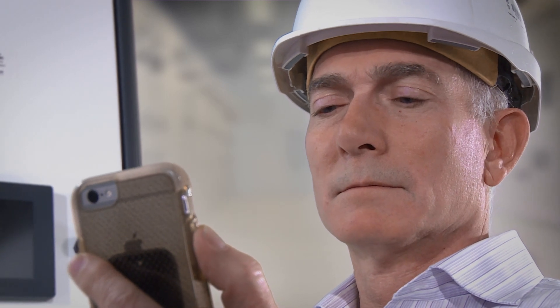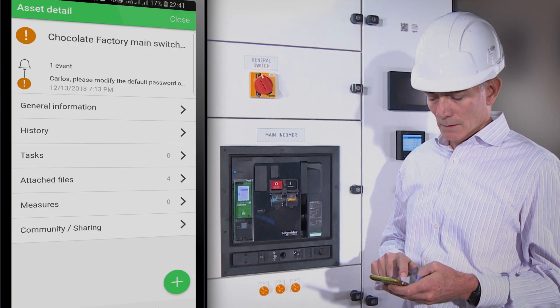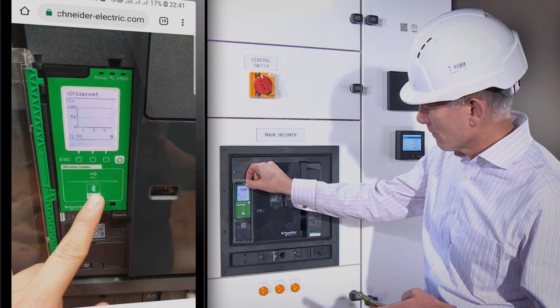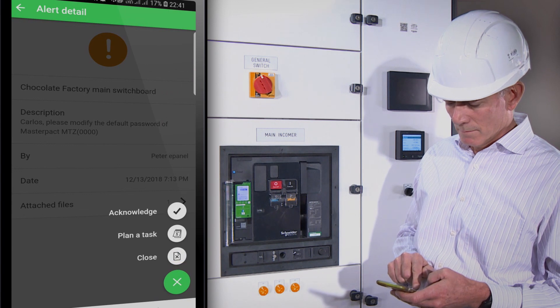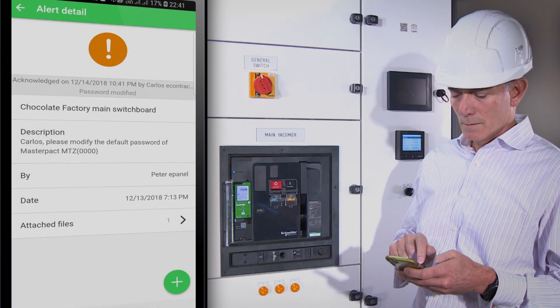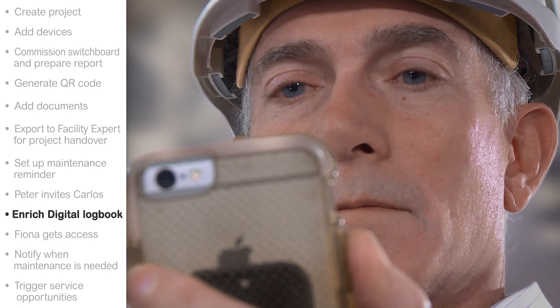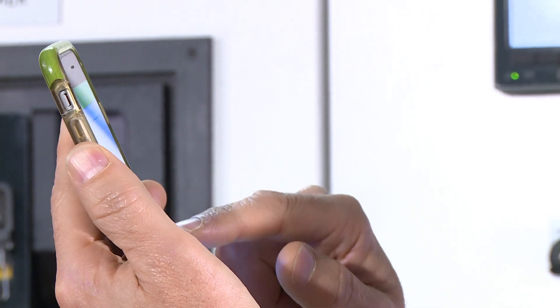Peter just sent me an invitation to access the project on Facility Expert. Now when I open the app, it takes me straight to Peter's project folder. As soon as I've commissioned Fiona's switchboard and finished a couple of final settings, I change the default MasterPact MTZ password following Peter's instructions. Next, I upload my final commissioning report, which is generated as part of the handover documentation for Fiona. What's great is that there's no longer any need to print out any paper documentation, because all documents can be accessed with the QR code.